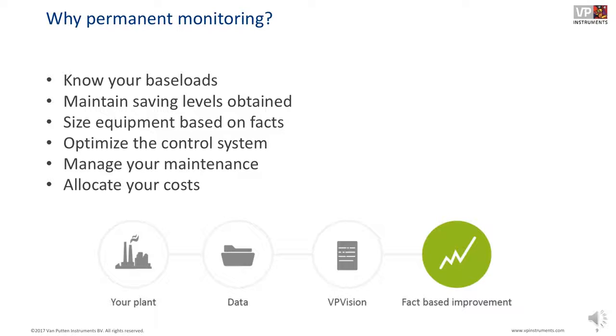Monitoring also helps you to manage your maintenance costs. By monitoring, you can spot system parameters go out of whack in time before it is too late, before you have that expensive shutdown because you have pressure drops throughout the plant that cause all machines to trip. So it helps you to get an early indicator when things go out of bound. You can call that service provider in time and look at a dryer, a valve, a piece of equipment which is valuable to you. Because without it, your production just stops.